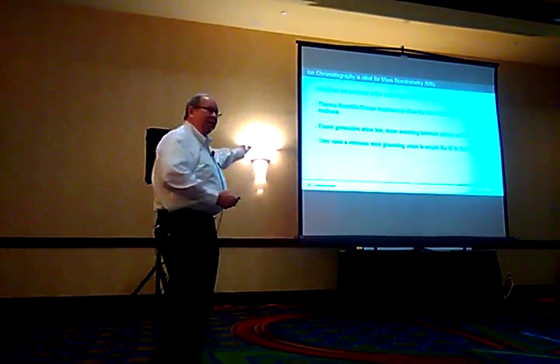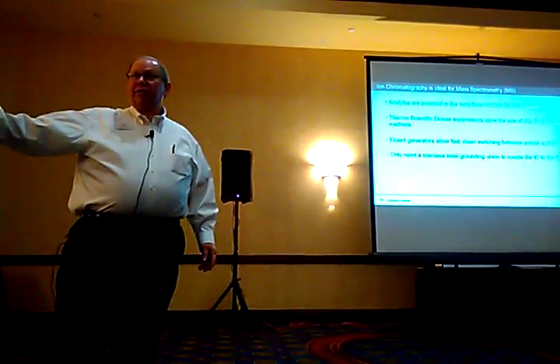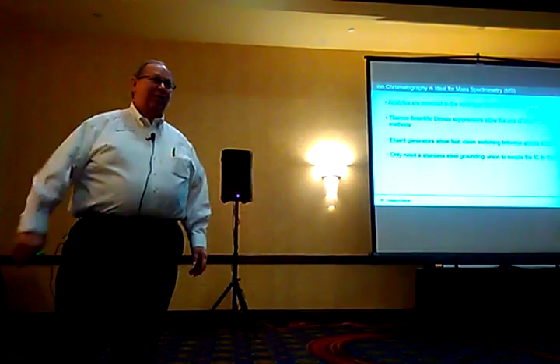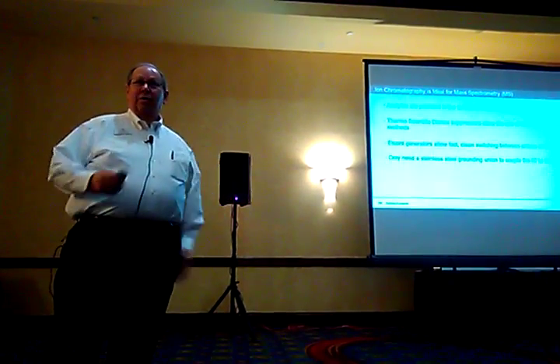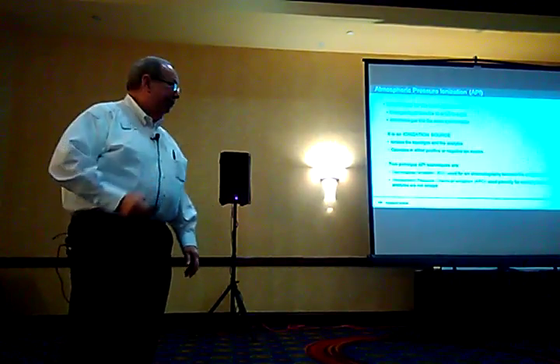That's all it takes to connect any ion chromatograph — whether it's an Aquion, an ICS-5000, a 2100, a 1600, or even a DX-500 if some of you are still using those. That's all you need to connect it to a mass spectrometer: a grounded stainless steel union.